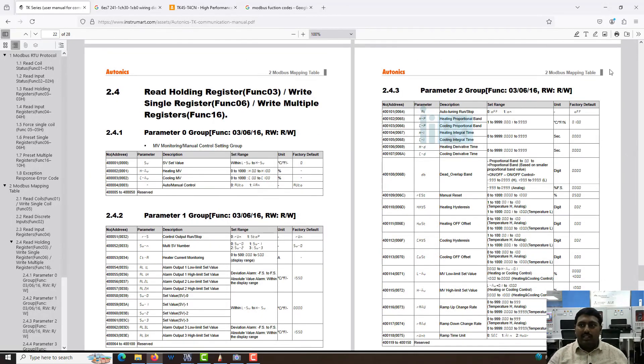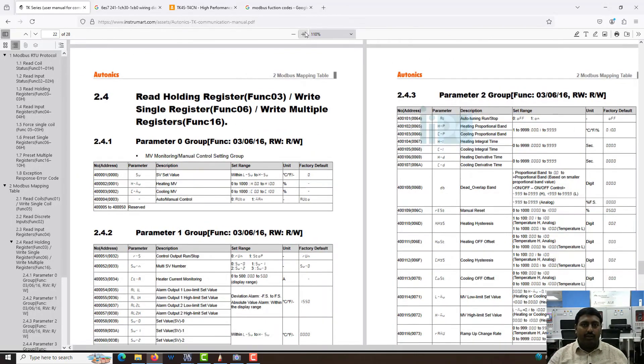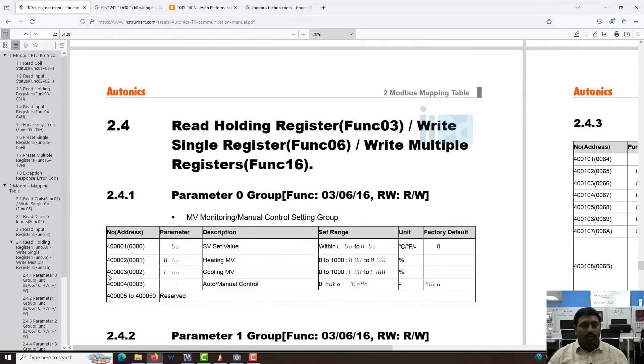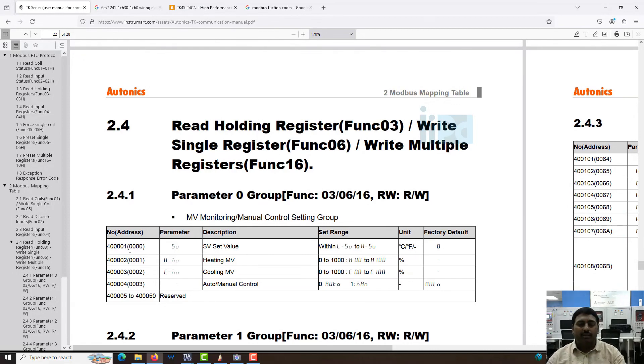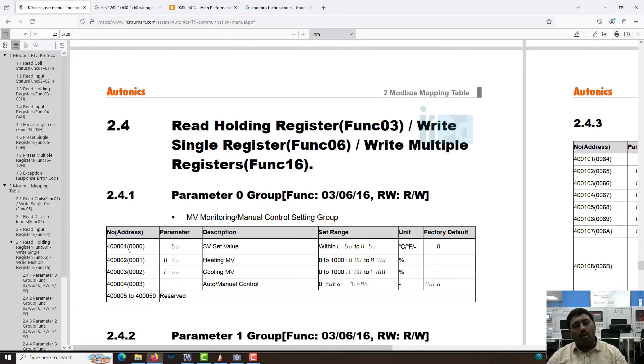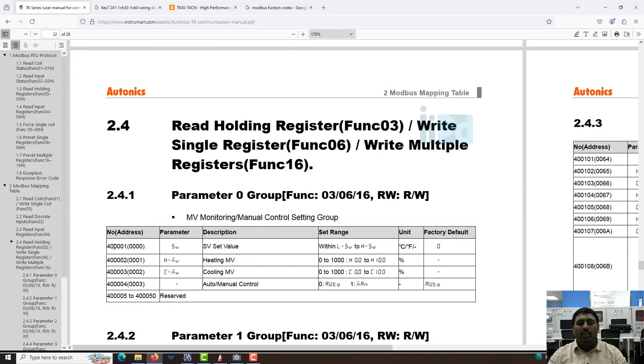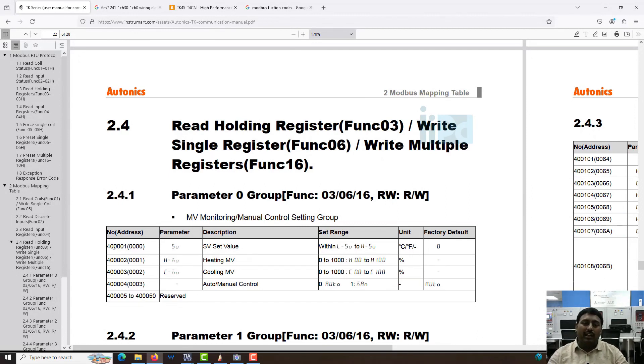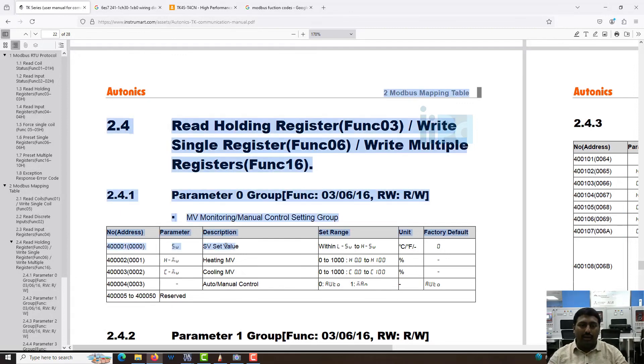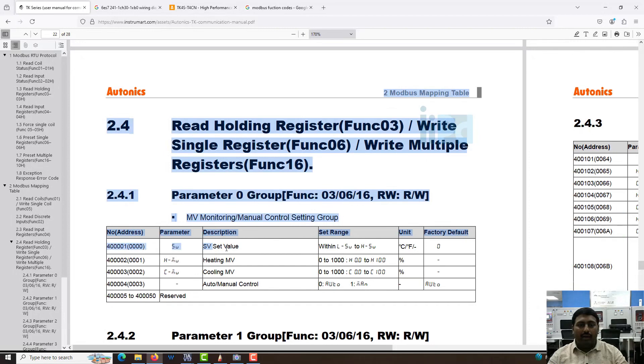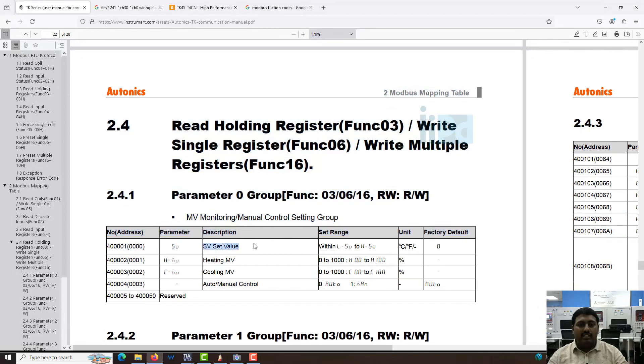Here you can see the set value at 400001. This is a six digit address. Since the second digit from the left is zero, you can cancel one of the digits. So you can just give 40001. That will be my set value.